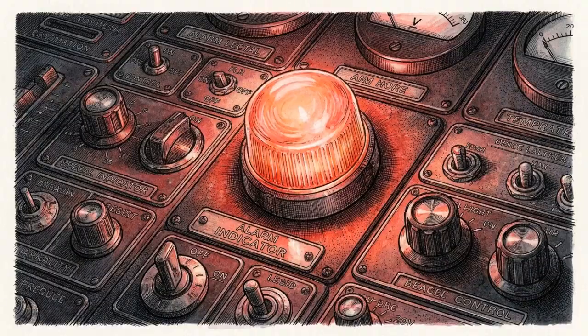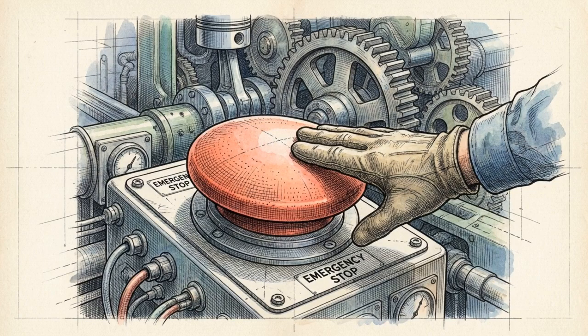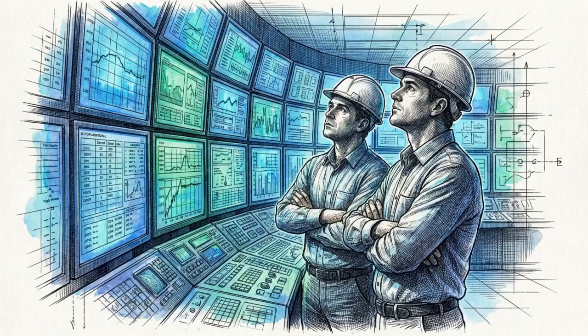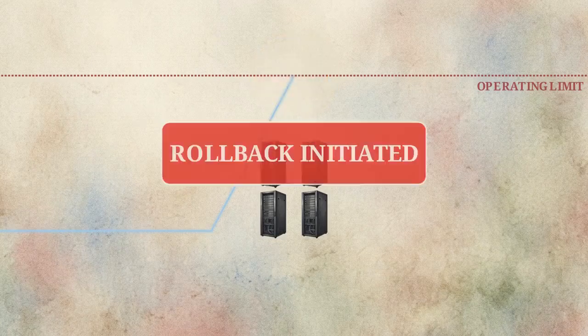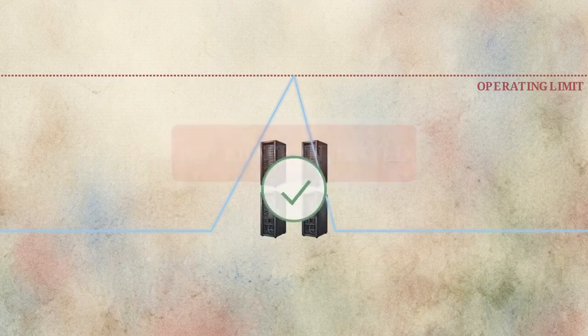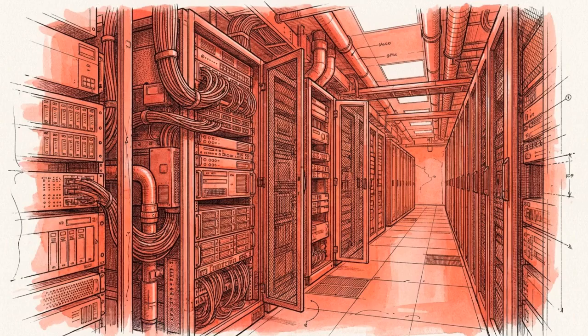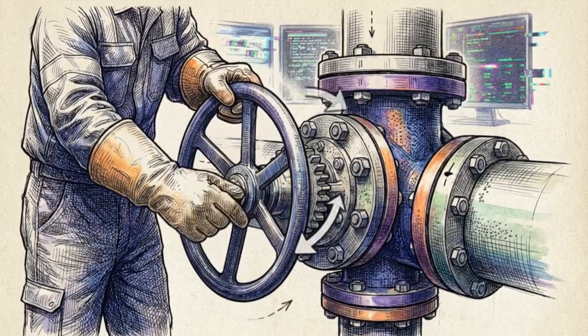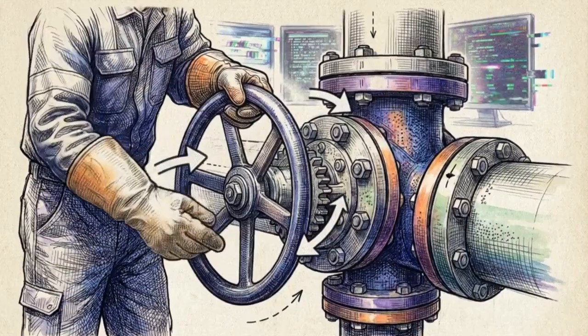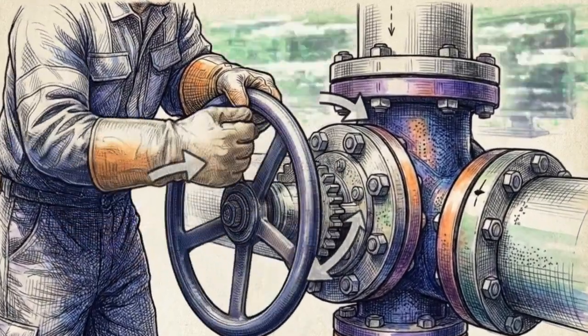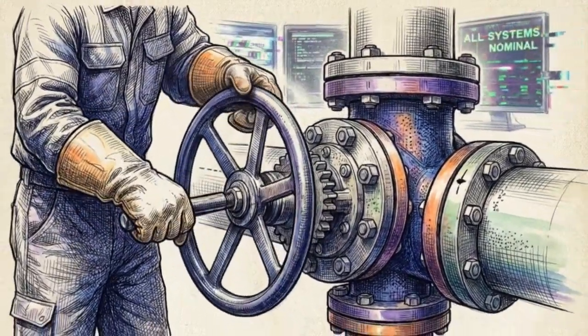Any loss of residual capacity, any unexpected alarm, or a single gap in test evidence mandates an immediate halt and a full reversion to the last proven state. Planned cuts test an engineering team's discipline, but those strict non-negotiable rollback triggers are what guarantee the facility's survival when operating limits are breached. In a total failure scenario, the prime directive takes over. Life safety and thermal stabilization dictate that operators rely entirely on local hardwired safeties, bypassing high-level software optimization loops to protect the facility.